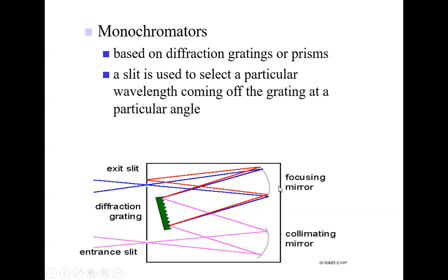Does that make sense? So sometimes when you hear the instrument scan, there are several things that happen, but a diffraction grating is going to tilt. And as it tilts, you're scanning the wavelength of light. Okay? So this diagram here has all the essentials of a monochromator. It has an entrance slit, a collimating mirror, a diffraction grating, a focusing mirror, and an exit slit.